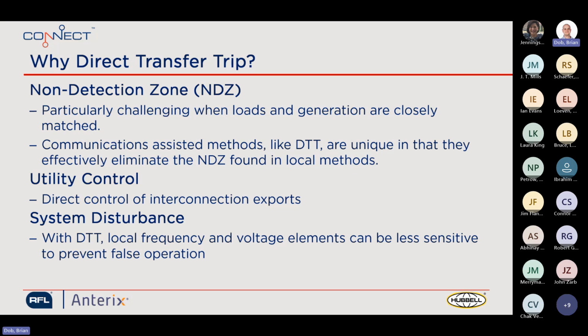And then a side benefit too is that with direct transfer trip, those local frequency and voltage elements that may otherwise be used to try to determine an island condition can be set less sensitive, and that also helps prevent false operation.